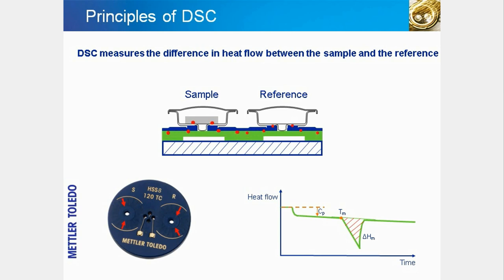In a DSC experiment, the heat flow from the furnace to the sample is measured relative to the heat flow to a reference material. The sample and reference crucibles are identical, except that the reference crucible is usually empty. In this particular heat flux DSC design, the sample and reference crucibles are heated from below. The sample is placed in a crucible, or pan, which sits directly on top of the sensor, surrounded by a heated chamber, or furnace. The sensor is the heart of the DSC and detects the heat flow. An enlarged view shows a Mettler-Toledo sensor with its typical star-shaped arrangement of thermocouples.